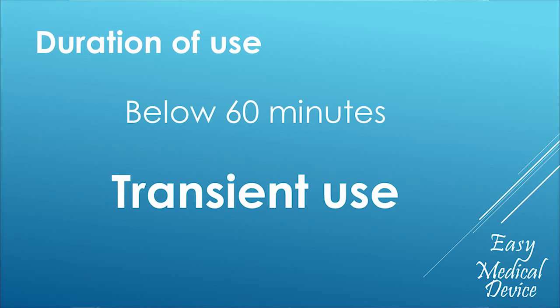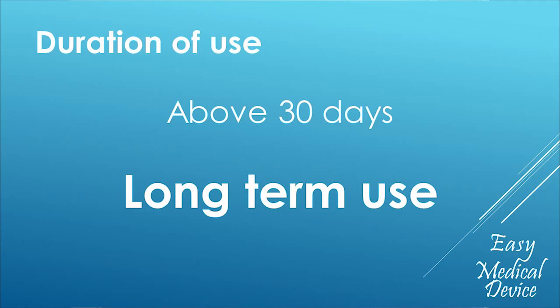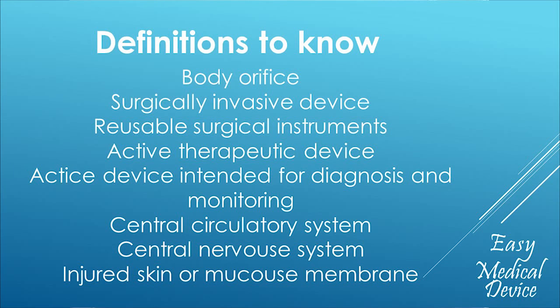There are some parameters you have to understand. First, it's the duration of use: if your product is used less than 60 minutes, it's transient use; between 60 minutes and 30 days, it's short-term use; and more than 30 days, it's long-term use. There are also a bunch of definitions you have to read — definitions about orifices on the body, what exactly is a surgical instrument, what is an active therapeutic device, etc. My advice is to read them, so when you arrive at a rule using one of those terms, you know there is a definition for it.